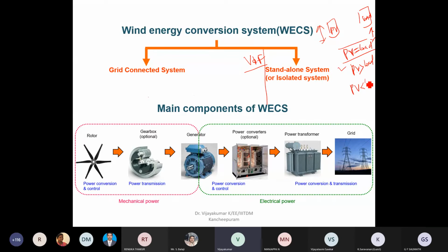If PV is less than load, is it possible to maintain voltage and frequency constant? Even though the load is greater, you have very little source, so it's not possible to maintain constant voltage and frequency. So what's the solution for it?